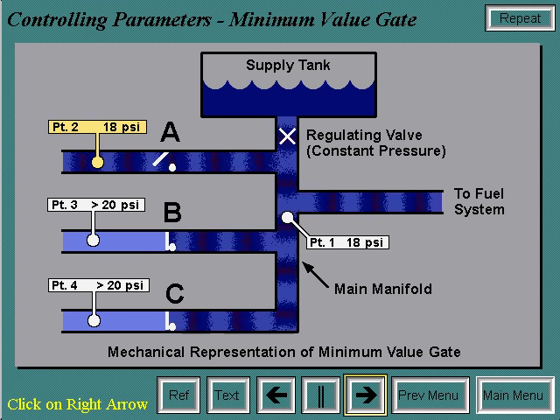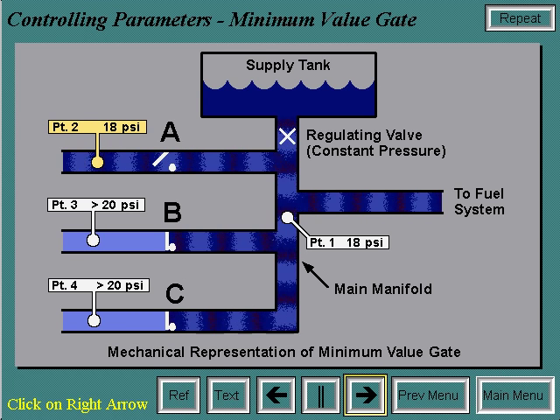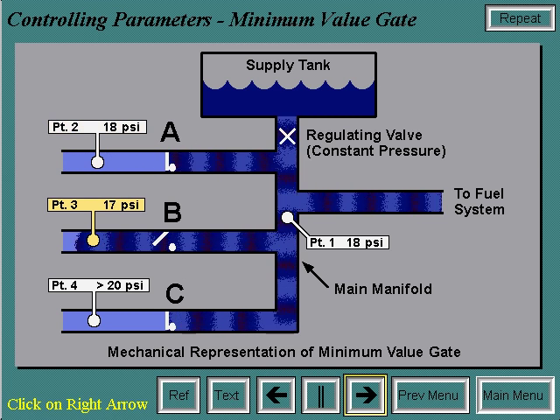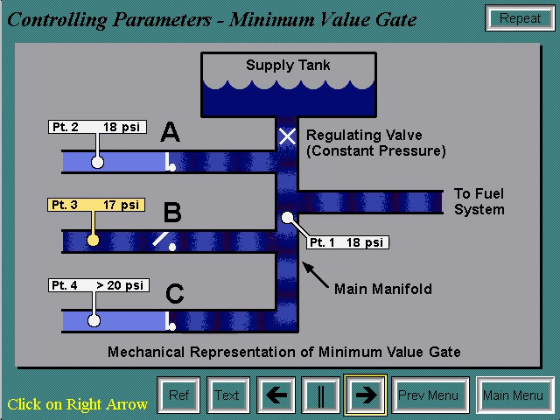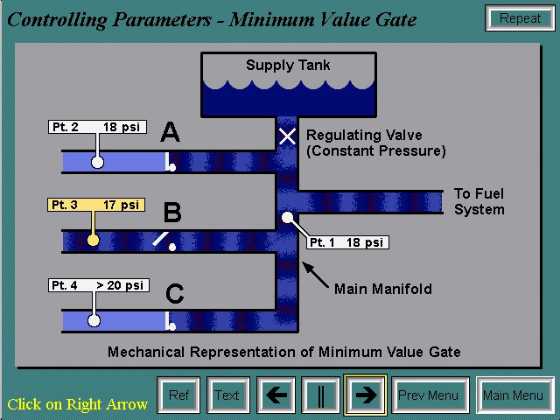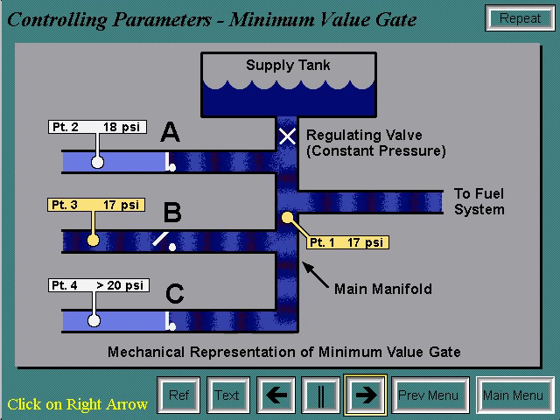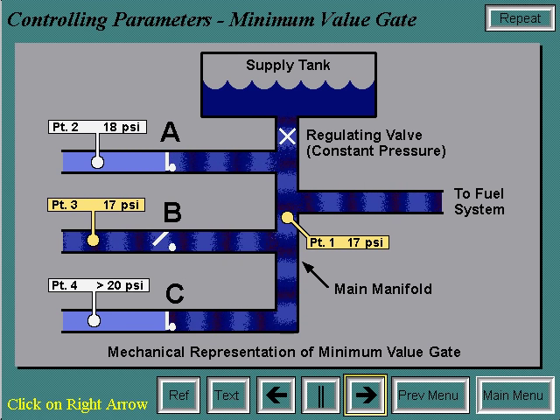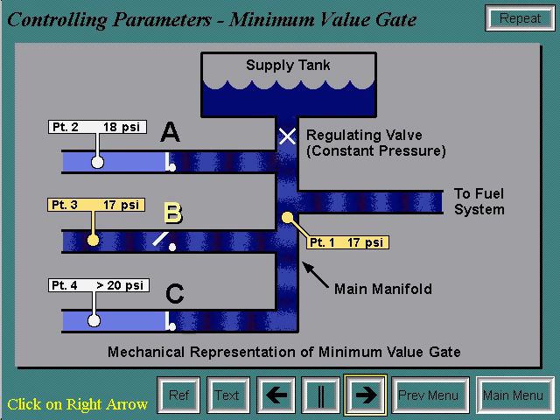As the operating conditions change, the pressure requirements at points 3 and 4 change. As the pressure at point 3 drops below 18 PSI, for example to 17 PSI, the manifold pressure will be brought down to 17 PSI, causing check valves A and C to close and check valve B to open. Therefore, system B is now controlling.